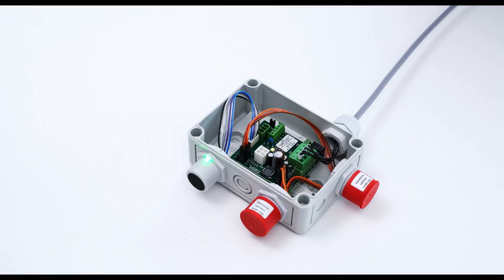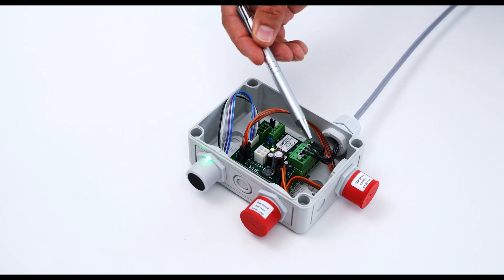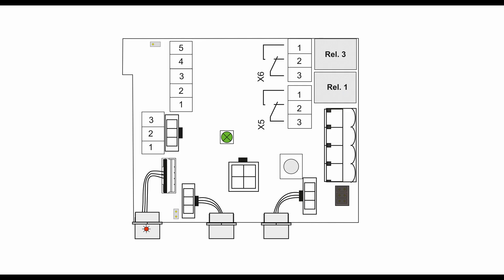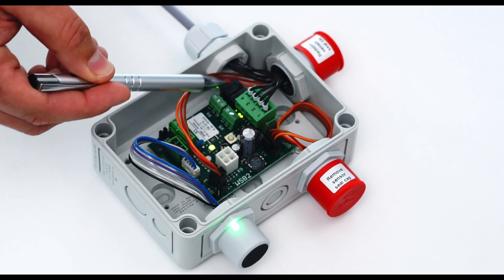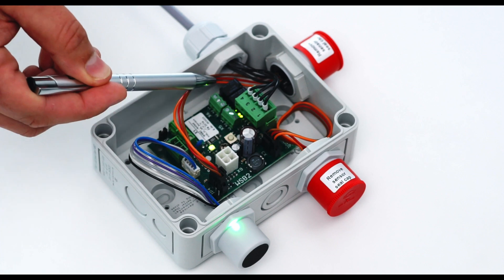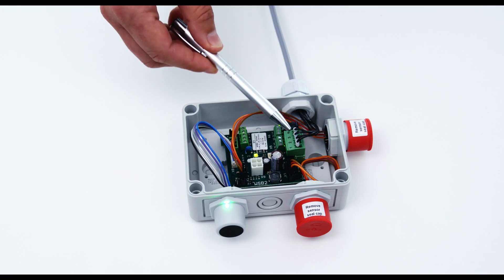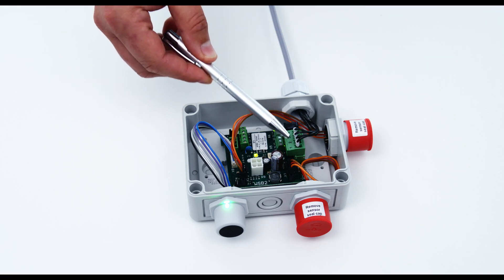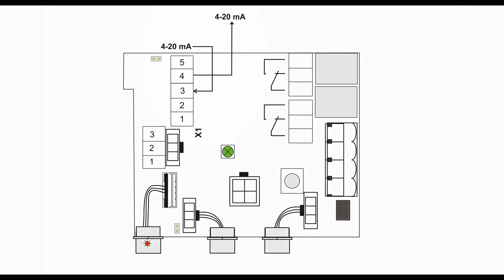The WSB2 has several interfaces for power supply, two relays which are freely selectable, an interface for Modbus communication X4.3 and X4.4 and for the 4 to 20 milliampere signal.